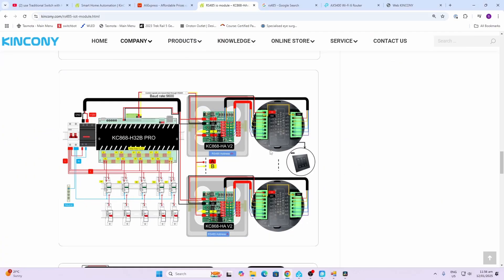The wiring is really simple. All we do is supply 12 volts to the device and then we run the A and the B and connect it directly to the A and the B on the unit. If we're connecting multiple units we would just keep daisy chaining them along the same bus.